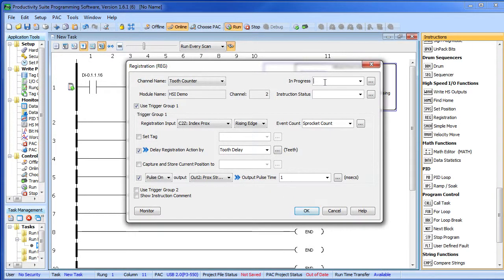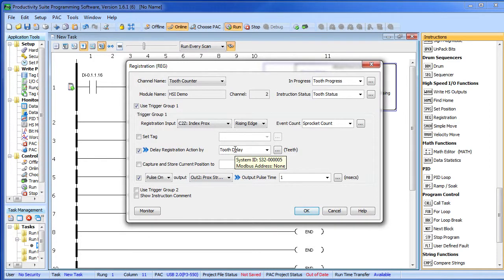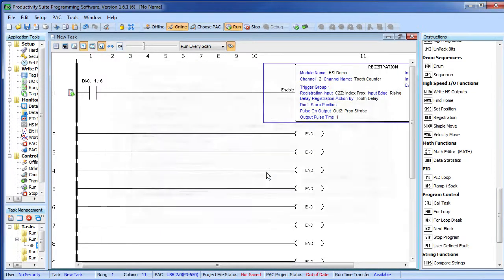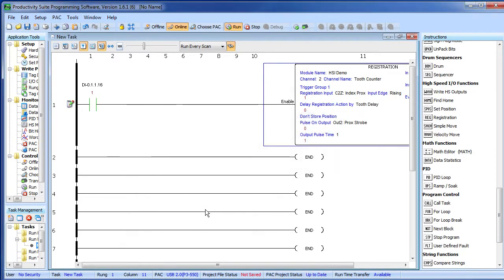Let's do one more thing – let's go ahead and create a tooth progress tag that will tell us whether the process is enabled or not, and let's create a tooth status tag so if we get any errors we'll know immediately. So we chose the correct channel, we're triggering on that index proximity sensor, we're keeping track of how many hits we get, we're going to delay the registration action by the number in this tag, and after the delay we're going to pulse our LED strobe. We'll say OK, add the new tags to our database, and all we have to do now is enable our instruction. I've already added a normally open contact connected to switch 16 on my input simulator so I can reach over to the P3 and enable this instruction manually. Let's transfer that to the controller and we're ready to go.